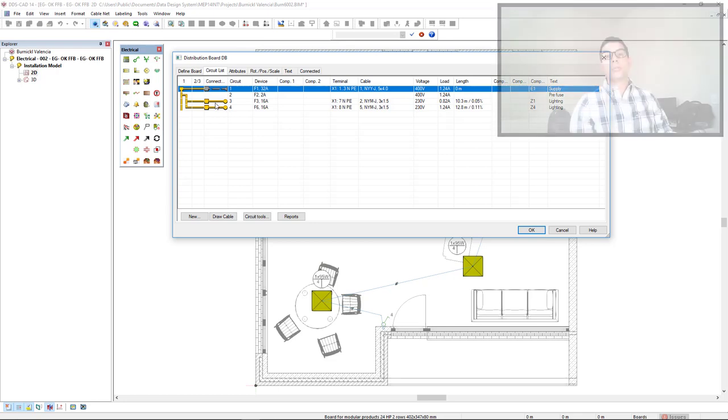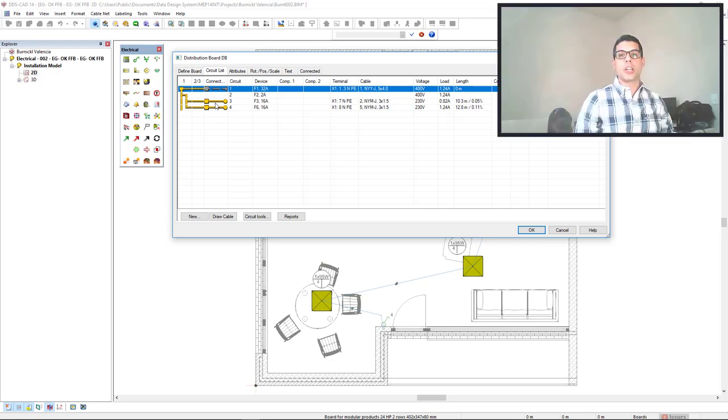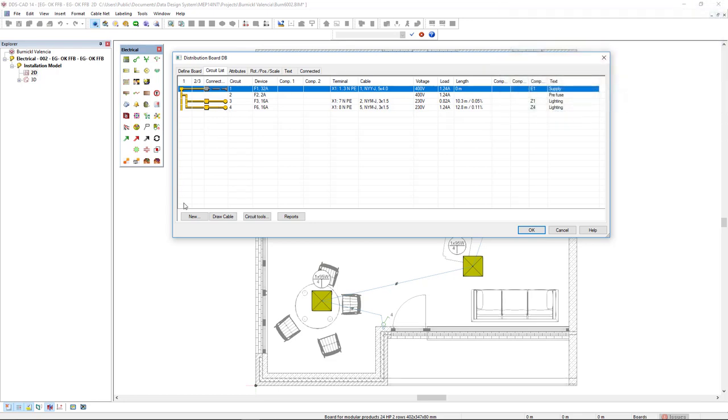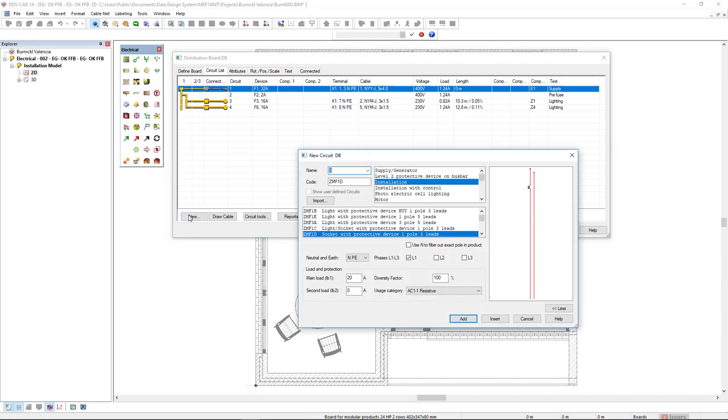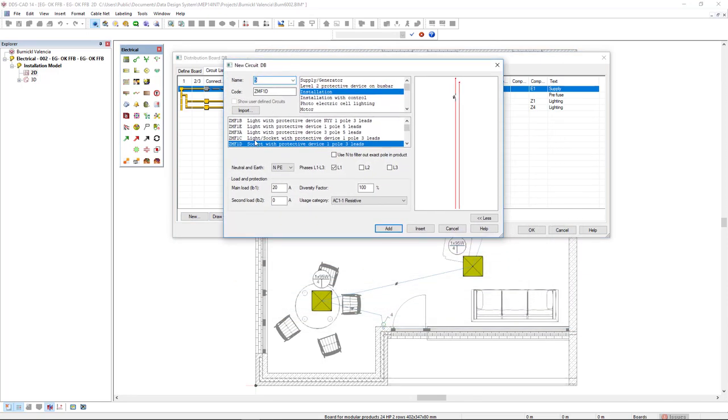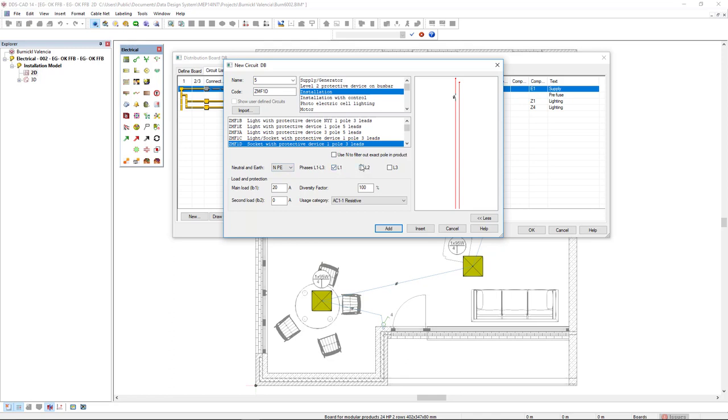Now, I will define a new circuit for socket. I'll click on New. And here, in the subcategory for installation, I will select the socket with protective device, one pole, three leads. We see here the options that we have available, such as the definition of a neutral and earth, and the number of phases. We can pre-define the load and the diversity factor, such as 50%.